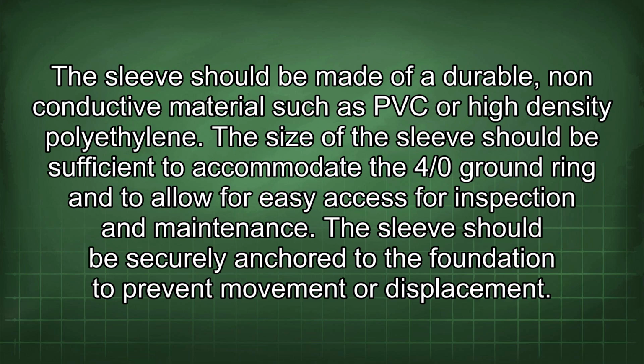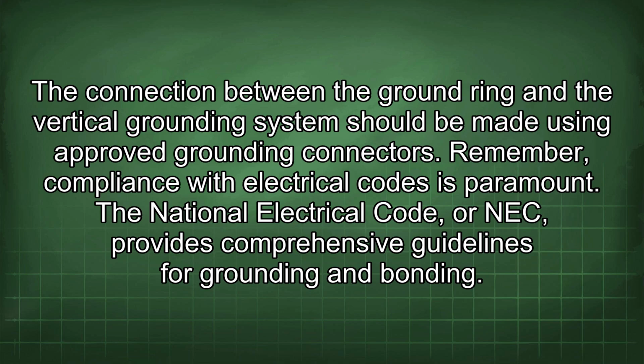The sleeve should be made of a durable, non-conductive material such as PVC or high-density polyethylene. The size of the sleeve should be sufficient to accommodate the 4/0 ground ring and to allow for easy access for inspection and maintenance. The sleeve should be securely anchored to the foundation to prevent movement or displacement. The connection between the ground ring and the vertical grounding system should be made using approved grounding connectors.